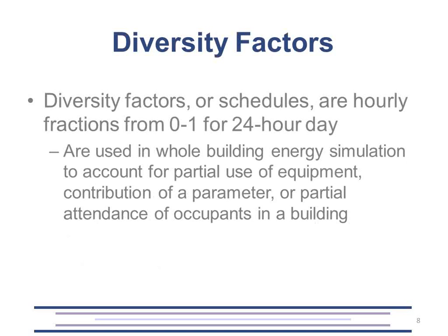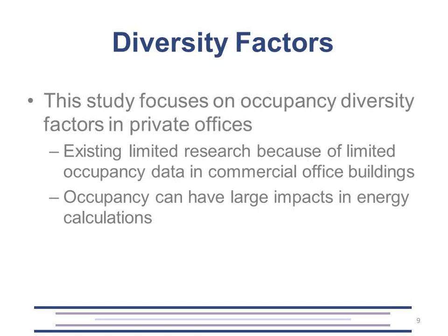Diversity factors, also known as schedules, are hourly fractions from 0 to 1 for the whole 24-hour period, and are used to account for the variation in the energy simulation that comes with weather conditions or occupants' attendance in the building. Occupancy is one of the diversity factors, and occupancy diversity factors are used to account for the partial attendance of occupants in the building.